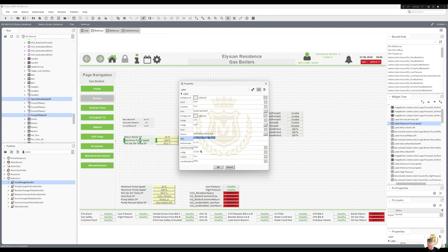Second maximum step size set point - I probably won't know what I mean by that, so I need to expand a little bit on that. Pump off delay, and I think we need to expand on that to say boiler or boilers, boiler pumps off delay because it's got all the pumps there. Second maximum step size, so that is modulation per second set point.